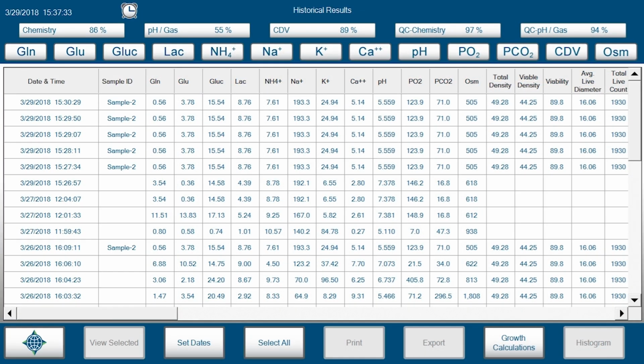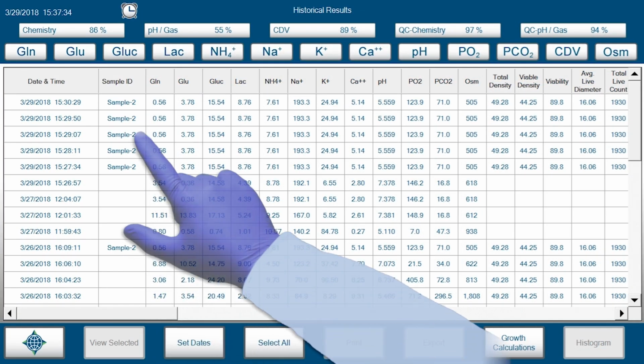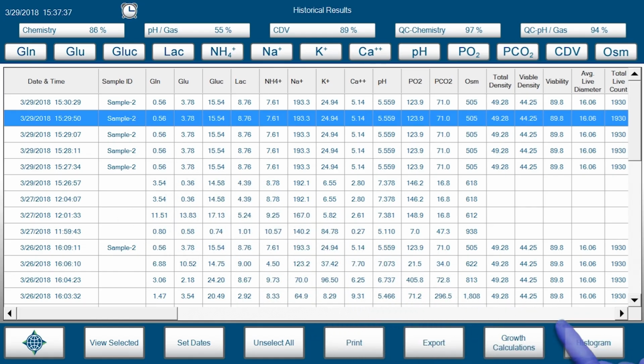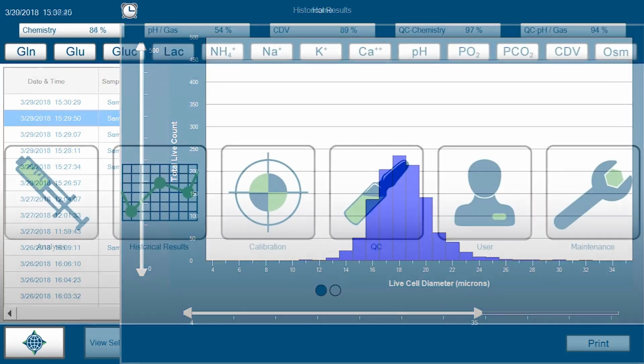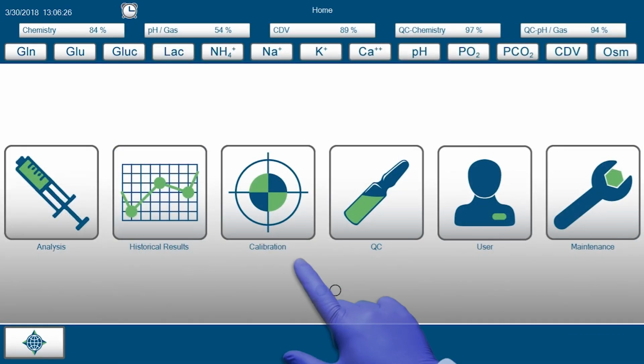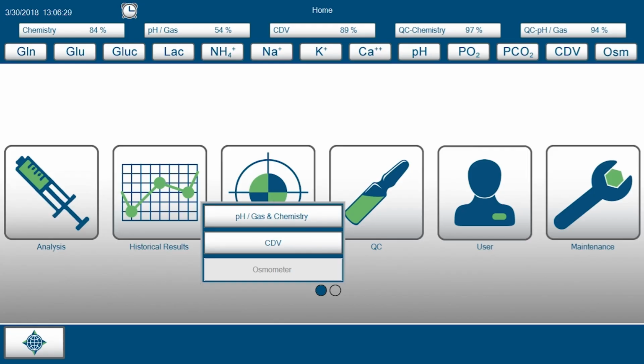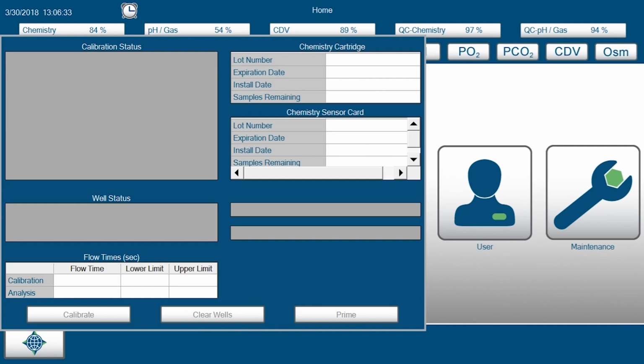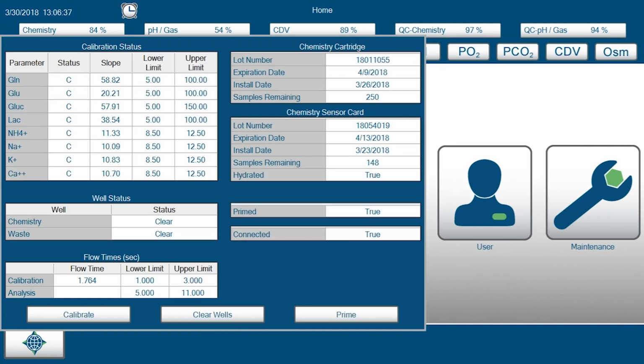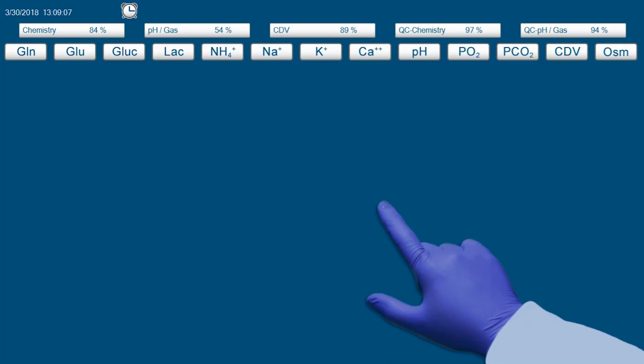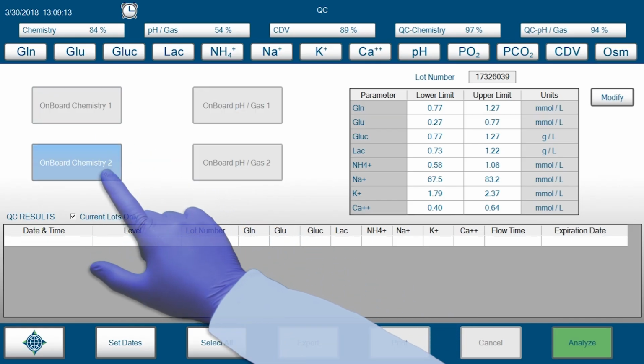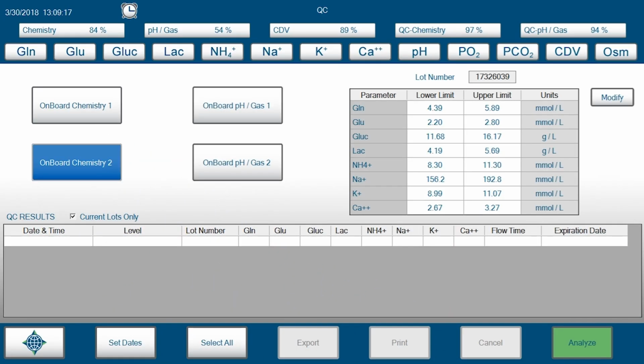You can also see a histogram of live cell diameter for a particular sample by selecting a sample and pressing the histogram button. The calibration menu will allow you to calibrate any of the modules included with your system. When calibrating from this screen, the pH gas and chemistry modules will calibrate at the same time. Calibrations can also be initiated from the module overlay screens. By selecting the QC button, the end user can view onboard QC data for the chemistry, pH gas, and osmometer. If onboard Auto QC cartridges are installed, QC can also be run from within this menu.